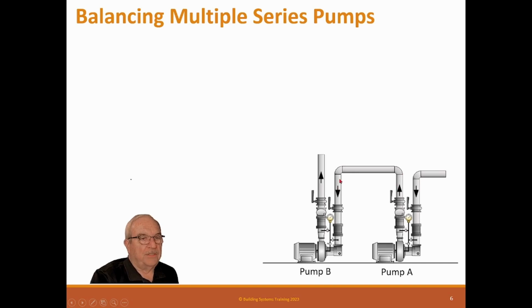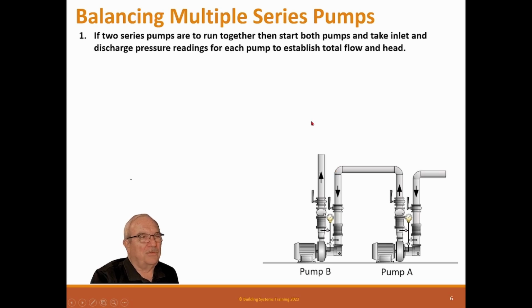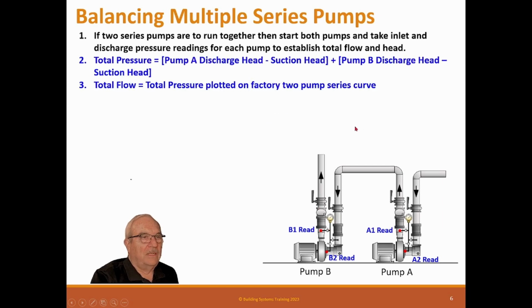So this is the series pumps one, and these are easy. They always run together. They don't run separately. So if 2 series pumps run together, start both pumps, take the inlet and discharge readings, and establish the total flow and head. So you turn both these pumps on and you take your readings. So here's readings 1 and 2, and a second and third, and then you add those together. Basically, that is how you get the total of the pump. So total pressure equals the pump A discharge head minus the suction head, plus the pump B discharge minus suction head. Total flow and total pressure are plotted on a factory 2-pump series curve.